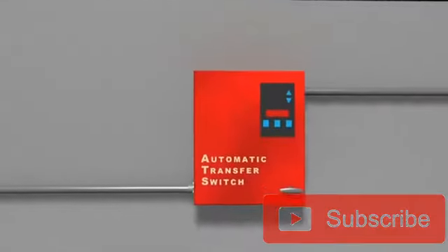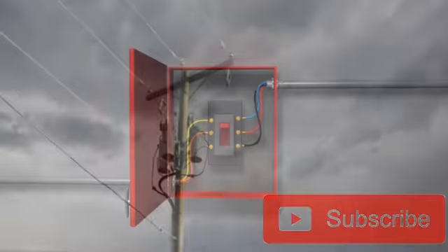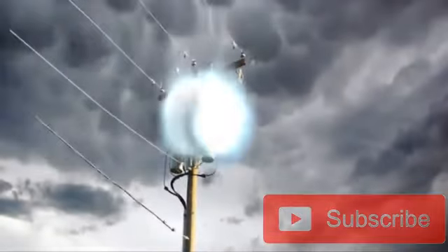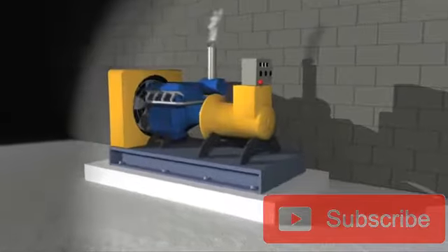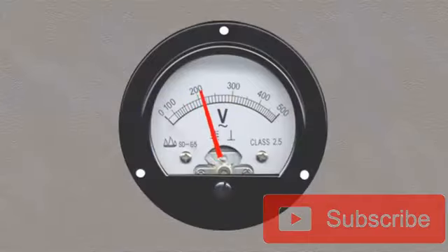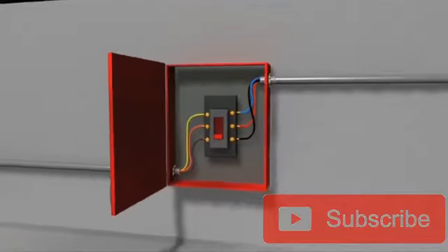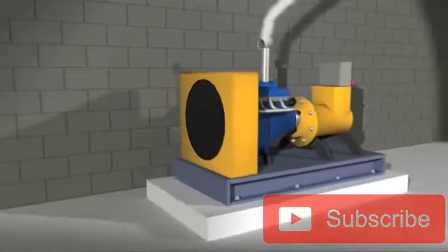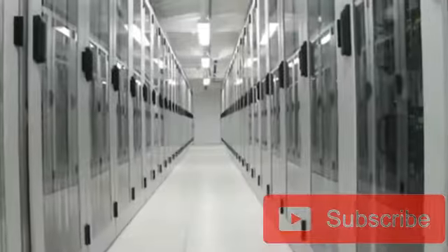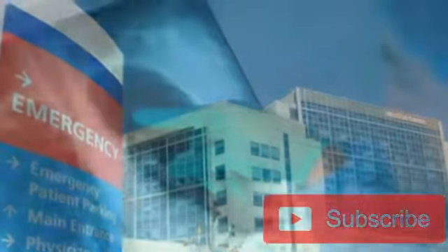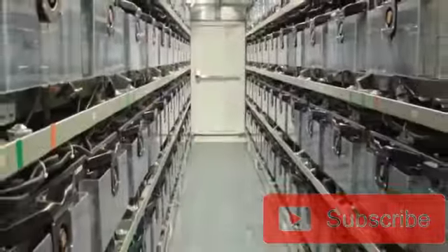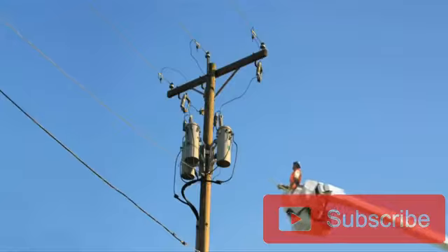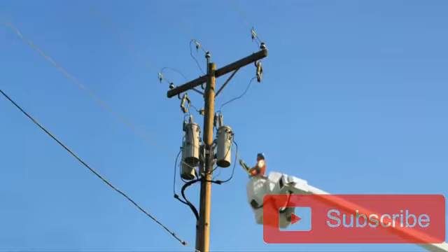An automatic transfer switch monitors the incoming power from the utility. If there is an interruption, it will send a signal to start an emergency generator. Once the generator reaches a desired voltage level, the ATS will switch over to the emergency power. There is a slight interruption in power from the time the ATS switches over to the generator from the utility power. In facilities such as data centers and hospitals where uninterrupted power is very important, a battery bank is in place to provide power until the generator is able to supply the correct voltage. Once the power from the utility is restored, the automatic transfer switch will automatically switch back to normal power.